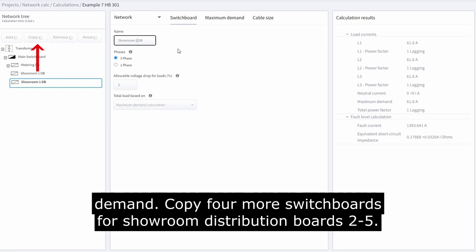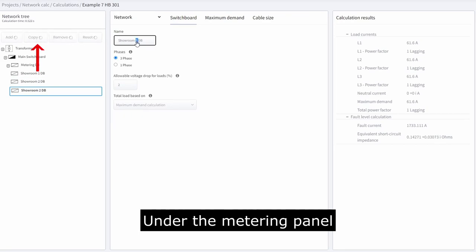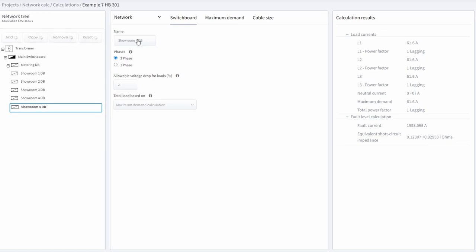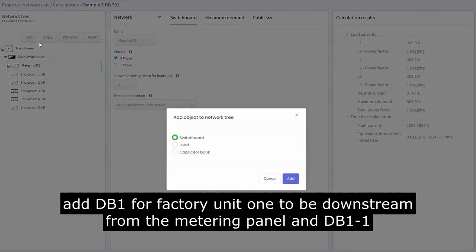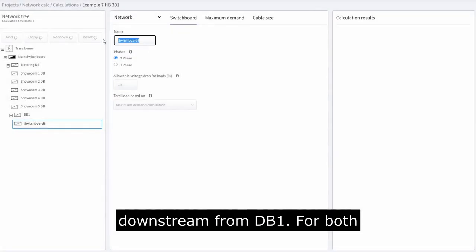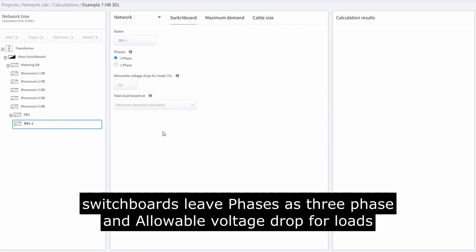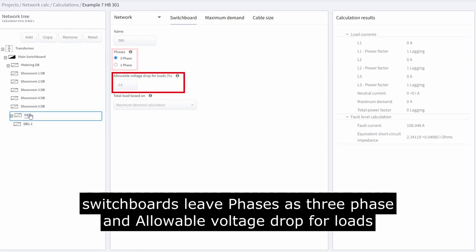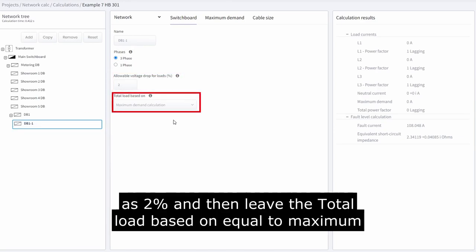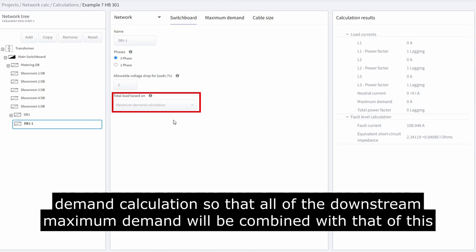Copy 4 more switchboards for showroom distribution boards 2 to 5 under the metering panel. Add DB1 for factory unit 1 to be downstream from the metering panel, and DB1-1 downstream from DB1. For both switchboards, leave phases as 3-phase, enter allowable voltage drop for loads as 2%, and leave the total load based on equal to maximum demand calculation, so that all downstream maximum demand will be combined with that of this board.